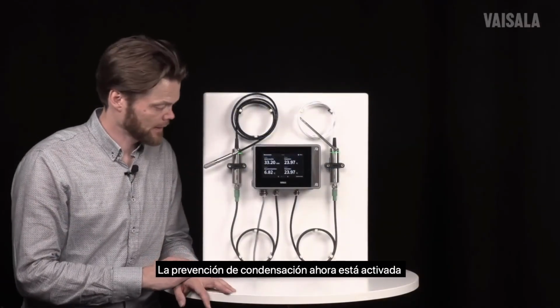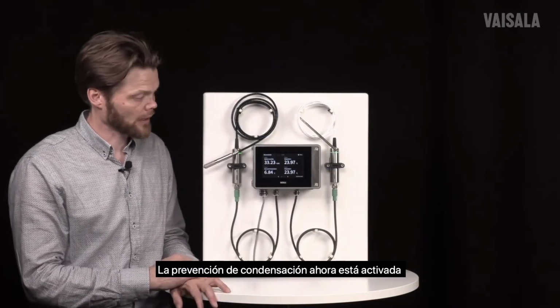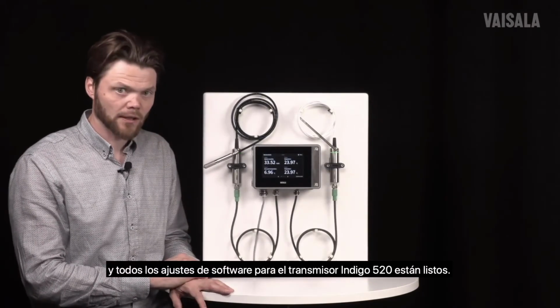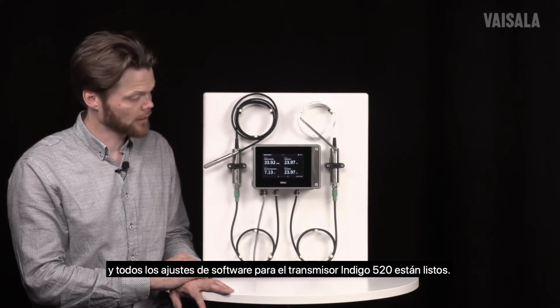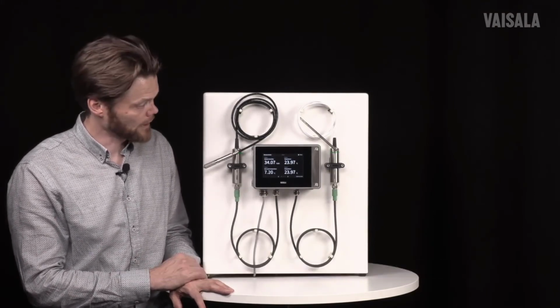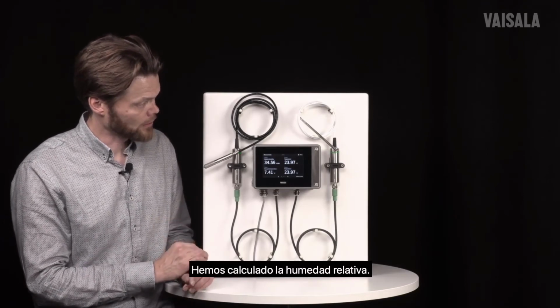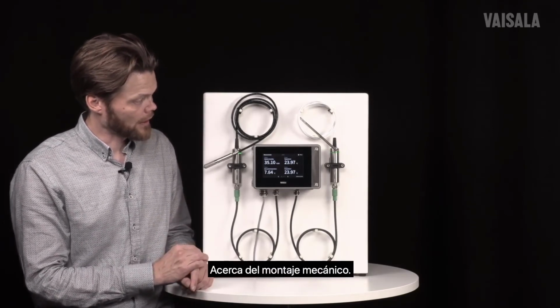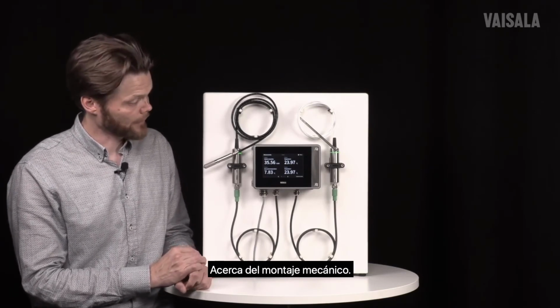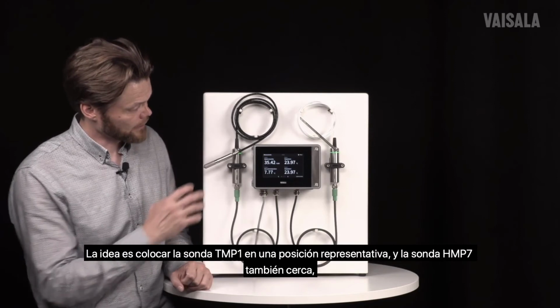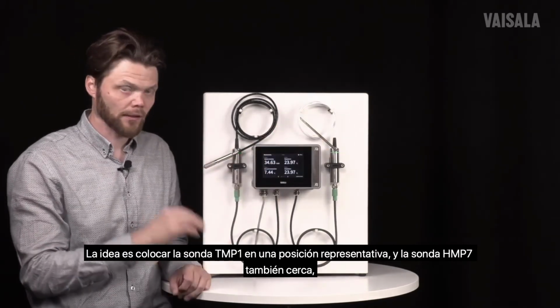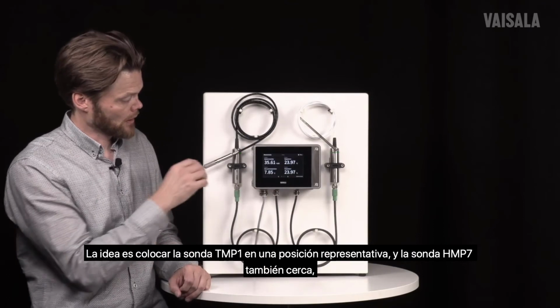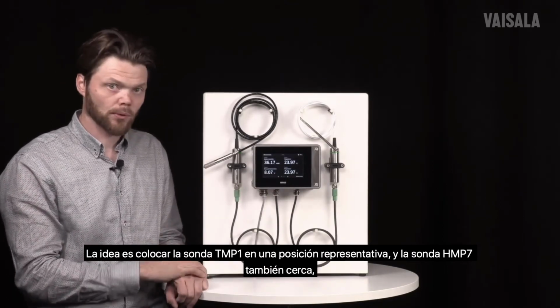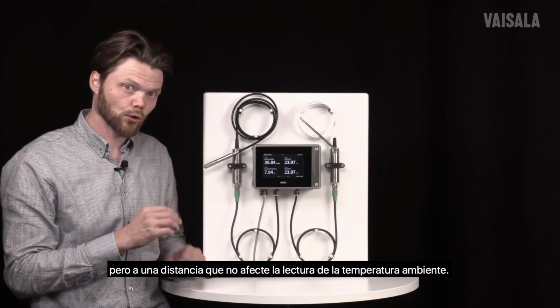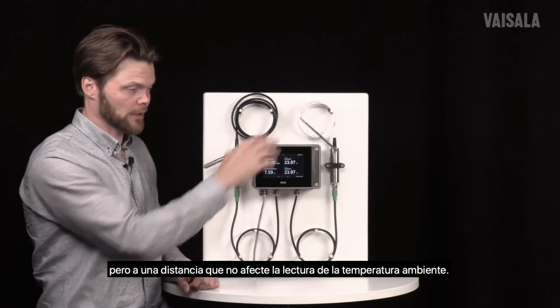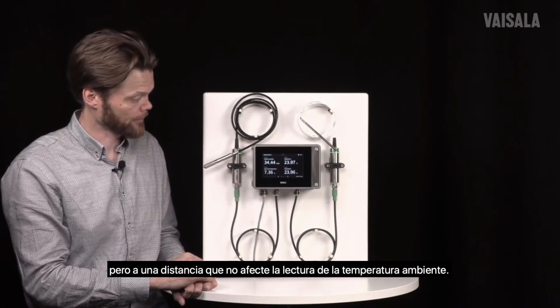Now we have activated the condensation prevention and made all the software adjustments for the Indigo 520 transmitter to calculate the relative humidity. The next thing is to consider the mechanical assembly. And now the idea is to get this temperature probe in a representative position, and also this humidity probe close by, not too close that it would affect the ambient temperature reading.